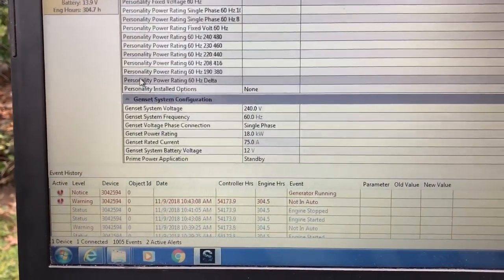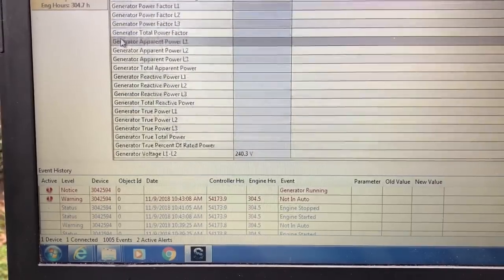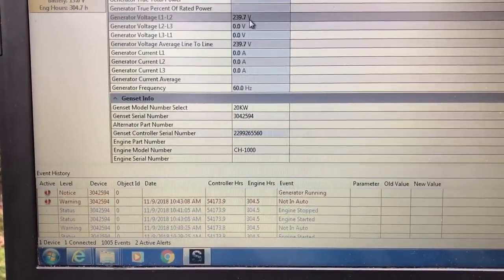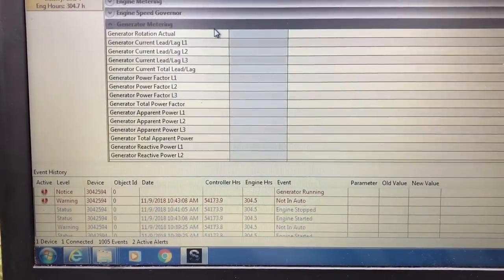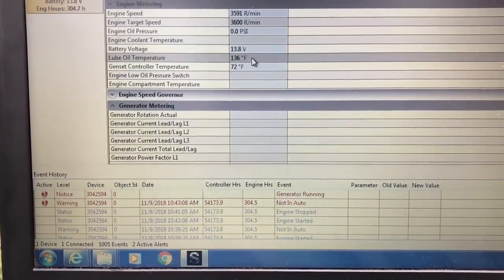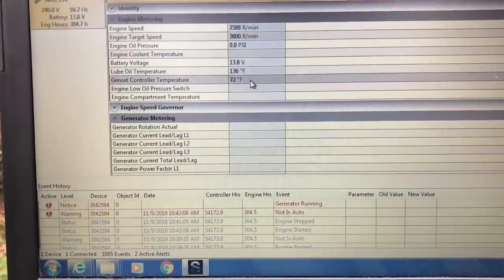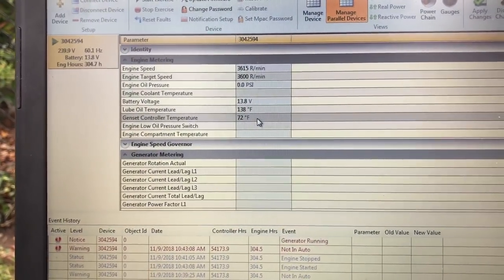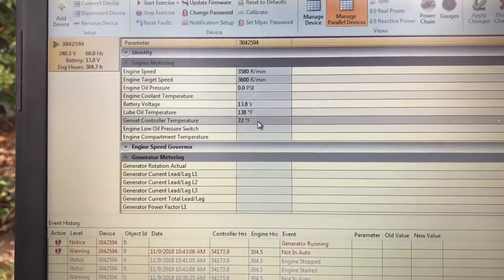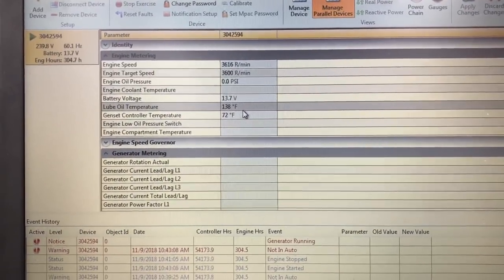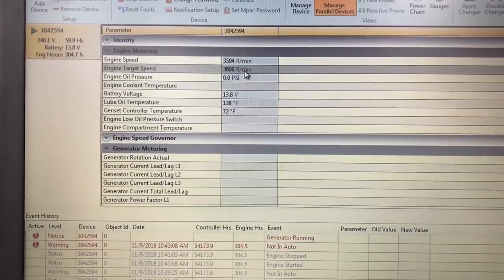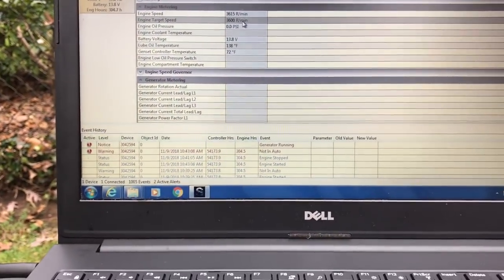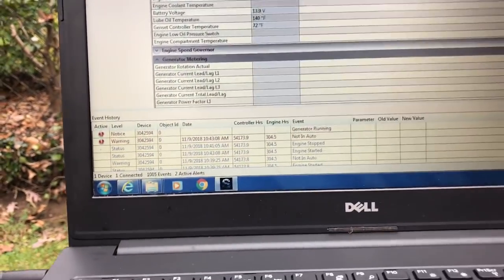I don't have anything really connected to my modbuses or any of this other stuff. I would have to have it connected to the internet for any of this to work. It's going to be on queue setup, but it's not. Alright, let's get back into the top part. Now, our metering, still putting out 240 at 60 Hz. Engine metering, right now our engine temp is 136 and the controller temp is 72. I like to warm it up this way so the oil drains out pretty quickly for me.